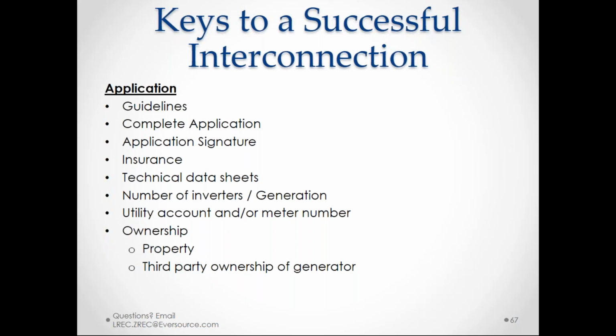We did originally try to restrict in the Power Clerk application, since you now have the ability to select the inverters, and that's the only way to build out the application, only being able to select inverters that met the new SA requirements. And we had to temporarily suspend that due to some issues we're having. That may get reinstated at some point, but since those new settings requirements have been put into effect essentially industry-wide, it is our expectation that all new projects henceforth should be utilizing new 1741 SA certified inverters that have those new IEEE ride-through setting capabilities.